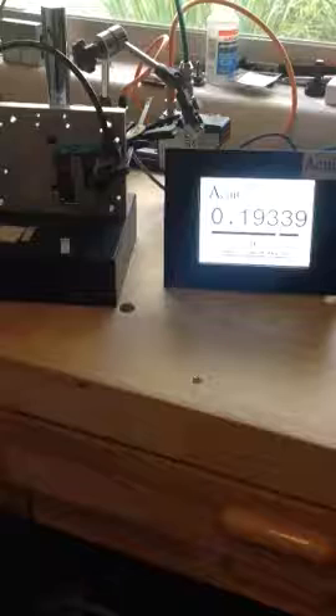This is just a quick little video showing the Acuity AR200-6 using our touch panel, and we've got it set up where we're going to show you how we do a quick calibration. Here you can see that we're within, this has a 0 to 250 thousandths range, and what we're going to do is we're just going to give it an auto 0 on this black granite stage, and this stage is probably accurate to, it's been polished to about 5 microns.